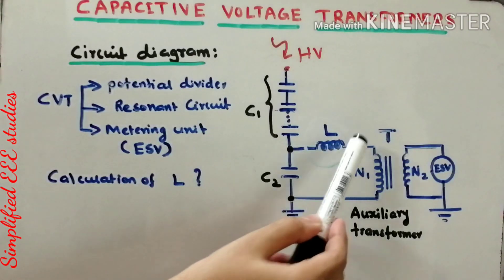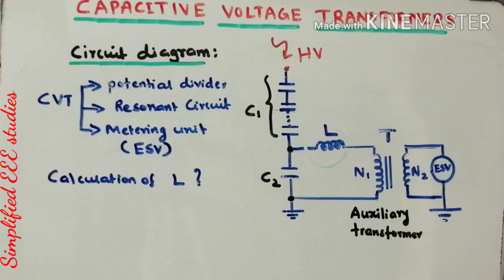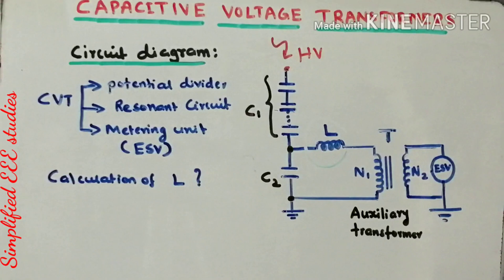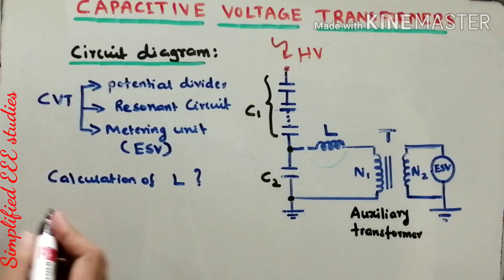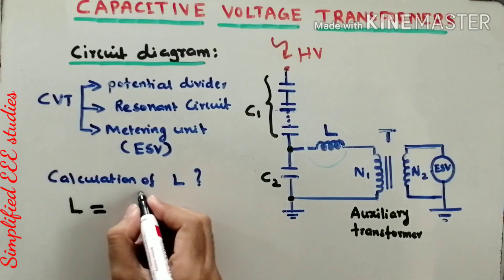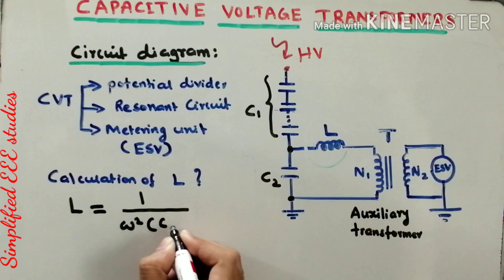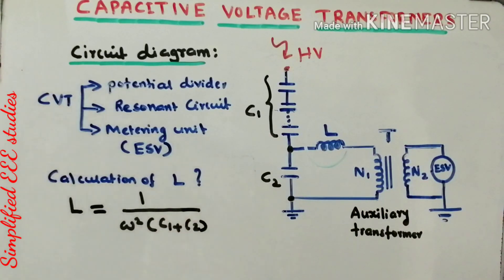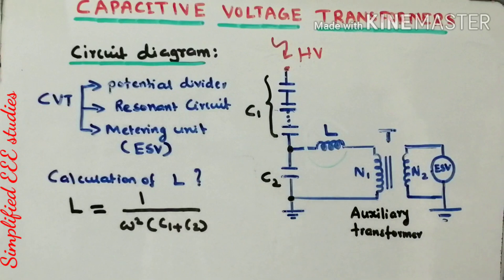To calculate the value of the inductor — which serves two functions: compensation for the transformer and avoiding inverted output — you can use the formula: L = 1 / [ω² × (C1 + C2)], expressed in Henry. Here ω is the angular frequency in radians per second, and C1 and C2 are the high voltage and low voltage capacitance values. After calculation, the inductor value can be adjustable and tunable to maintain the suitable value.